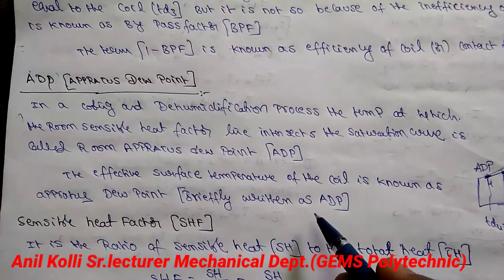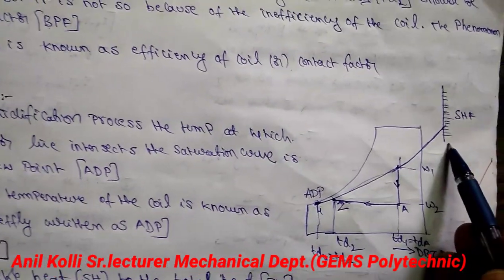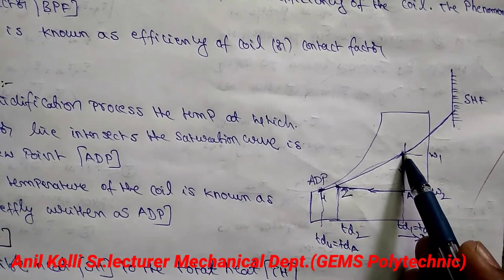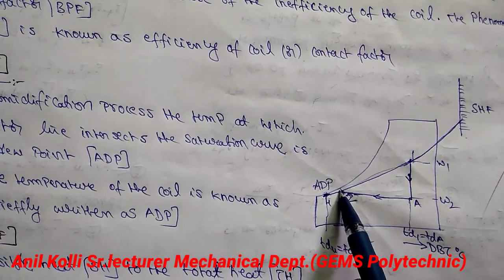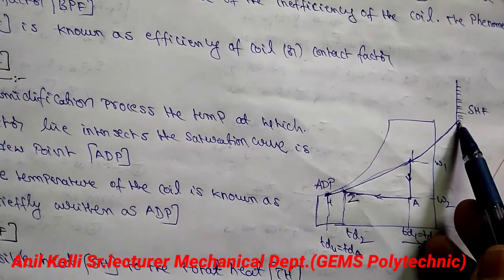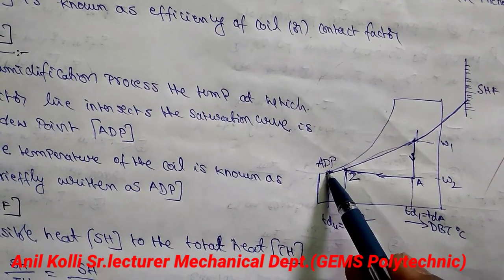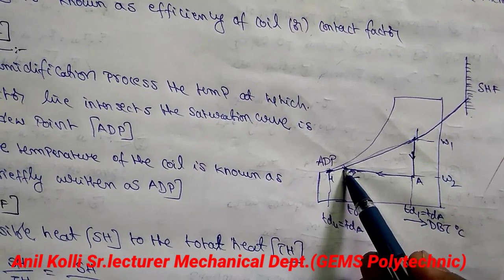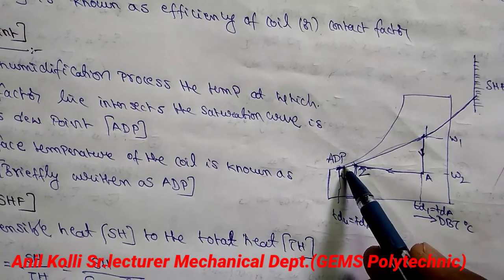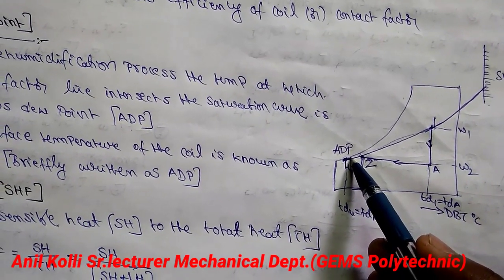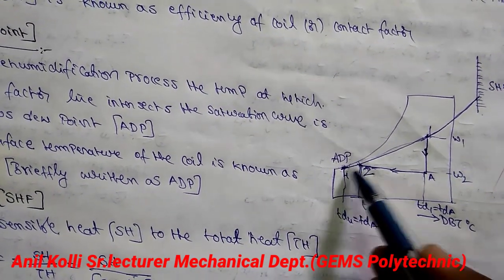In the cooling and dehumidification process, let us look at the psychrometric chart. Suppose process 1 to A is a dehumidification process and A to 2 is a cooling process. The sensible heat factor line, if extended to the saturation curve — though practically not possible due to coil inefficiency — where this line intersects the saturation curve gives us the ADP, i.e., the apparatus dew point.